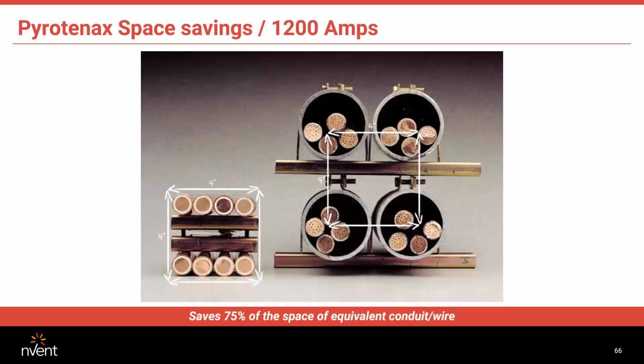This is a good slide here. And I always ask engineers and contractors, of course, MI cable is a natural for fire rated applications. But keep it in mind for non-fire rated applications, because maybe once or twice a year, you may be working in a situation where space is at such a premium that you don't have room for pipe and wire. Say, for example, you have a 1200 amp feed that has to fit through a 4-inch square opening. With pipe and wire, you're going to need 4 runs per phase of 500 or 600 kcmil, and you won't be able to do it.